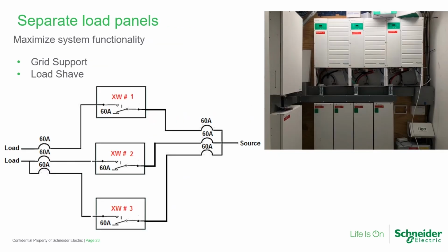Of course, when grid support and/or load shave functions are desired in a multi-unit system, these functions are available if it's possible to split up the loads. Here you see a picture of a system in Massachusetts where they have one power distribution panel dedicated to 2 inverters and then a second power distribution panel dedicated to the third inverter. This will allow you to eliminate external switching and have full functionality of the platform.